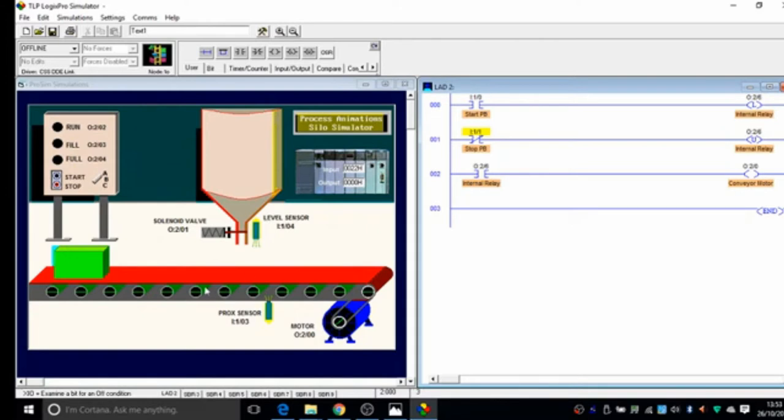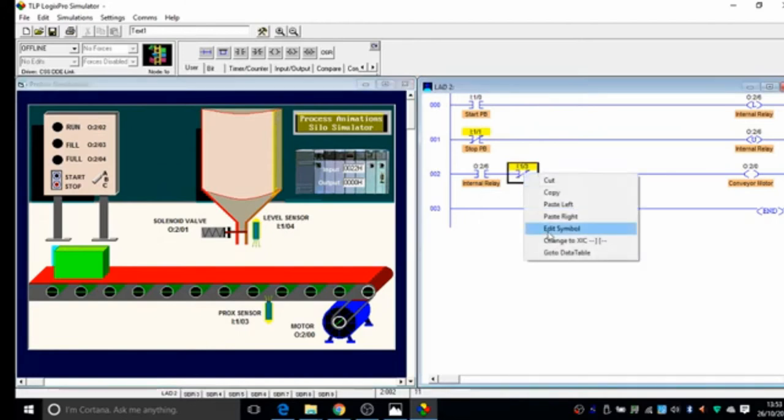What we want to do is when it gets to this I13 sensor proximity switch, as soon as it sees the edge of the box, we want to stop the conveyor. So we need a normal closed contact of this input here. So I'm going to go ahead and put a normal closed contact here, put it in the right logical order, and drag this input, put it there. You can just type, it doesn't make any difference, and then type the description of it.